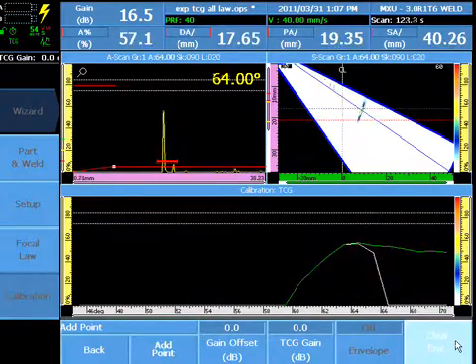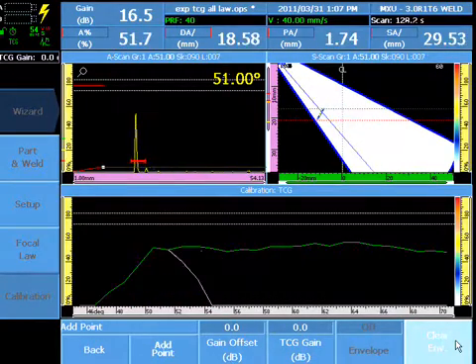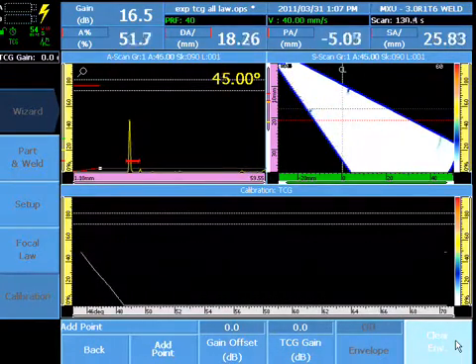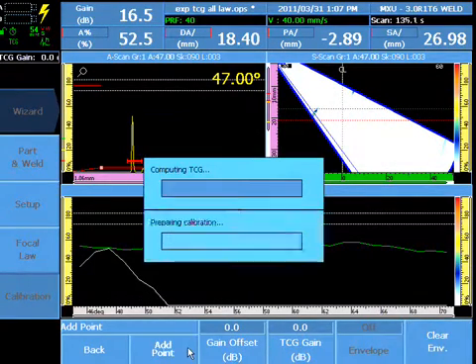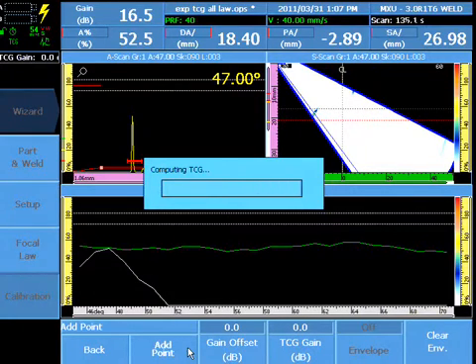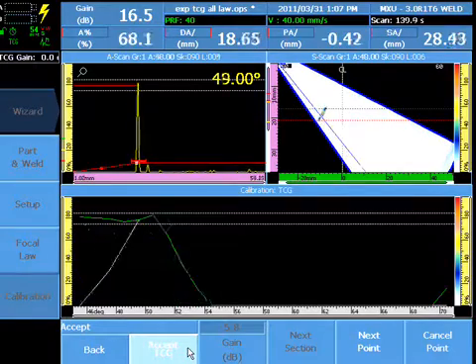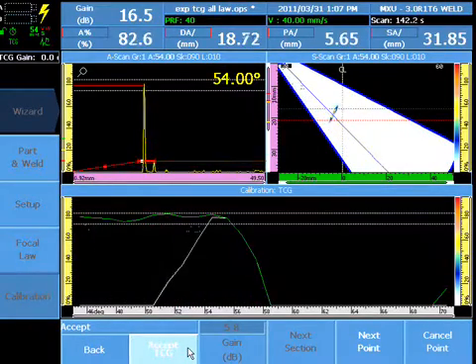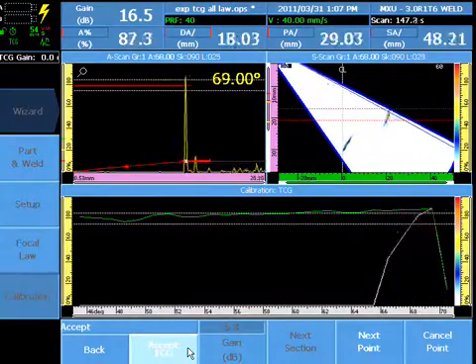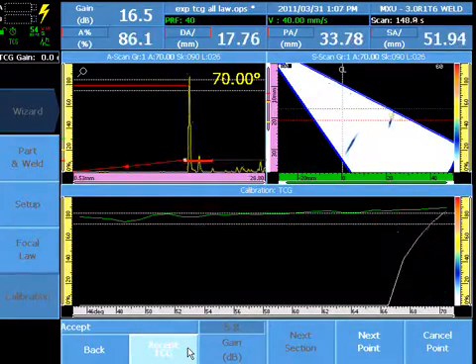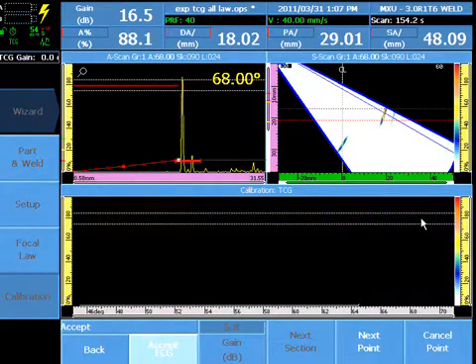Move the probe over the second calibration target so that all focal laws are exposed. Add the point. Verify that the calculation has every focal law at the correct amplitude. The point can be repeated when the calibration is out of tolerance.